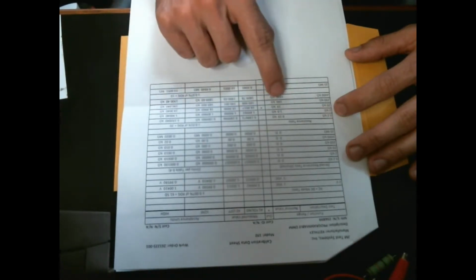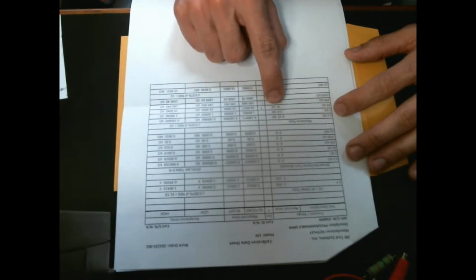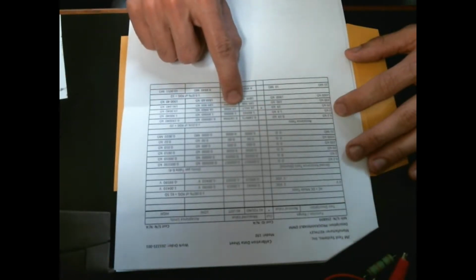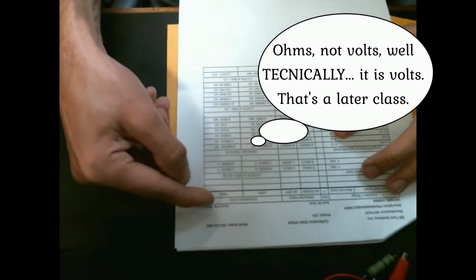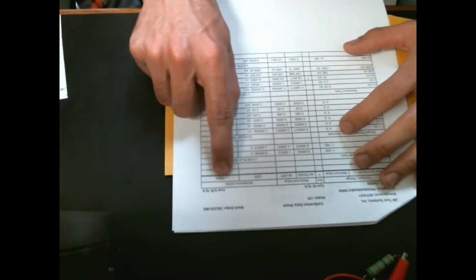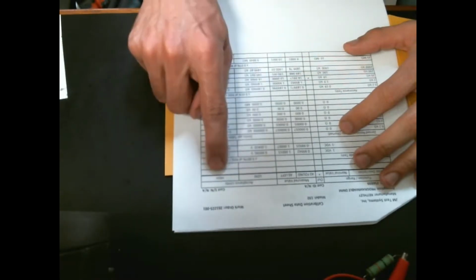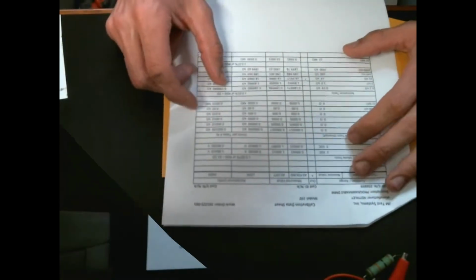So if I put a high precision 19 kilo ohm resistor on there, I should see that precise 19 kilo ohms. Now if you look along these two columns here, these are more or less just the references to show you if you're below or above or within spec. And you can see here accepted limits, and then there's a low accepted limit and a high accepted limit. And as long as you're in between those two numbers, your meter is within spec.